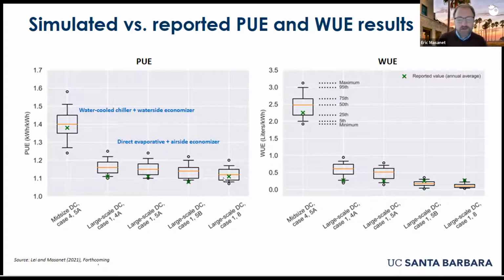The model did a pretty good job capturing the reported value through its predicted median, only off by about 5 to 10%. For a mid-size data center running a water-cooled chiller with a waterside economizer, the model performed quite well. Because we can now model the physics of the systems—the airflow, the water flow, the temperature, the thermodynamic properties of the fluids—we're able to use these physics-based models to get a pretty good estimate of PUE for existing data centers.